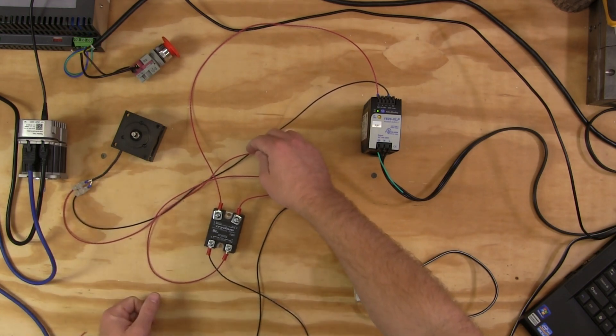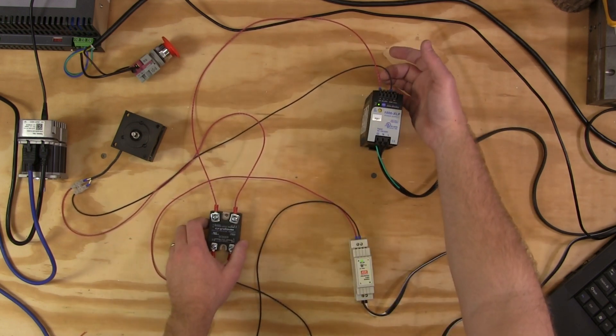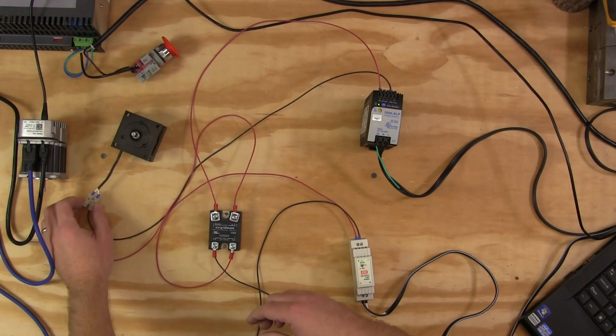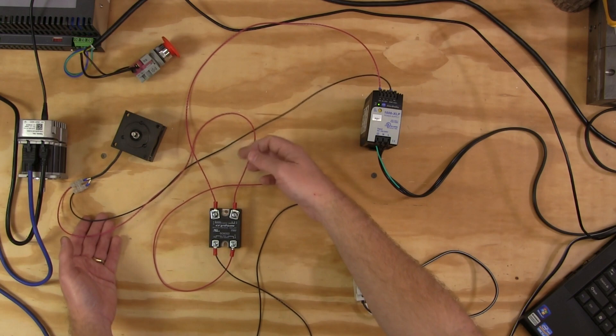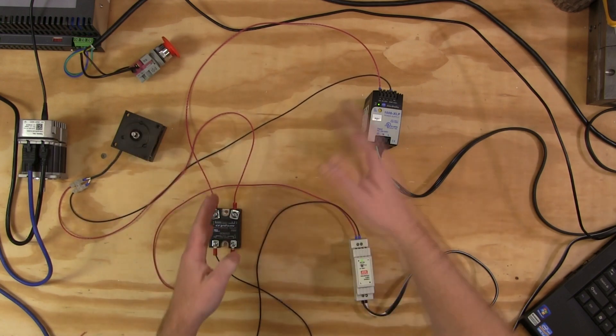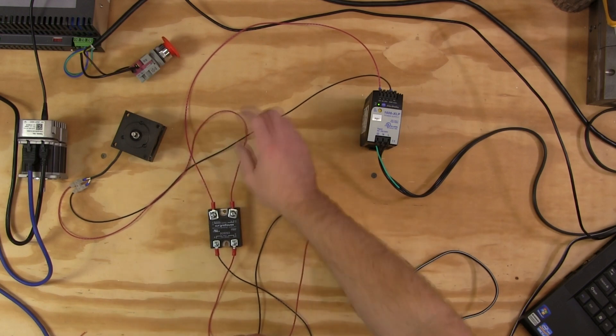The negative 24 coming out of the power supply goes directly to the other connector on the brake. So all the relay is doing is breaking the positive 24 in between the power supply and the brake as seen right there.